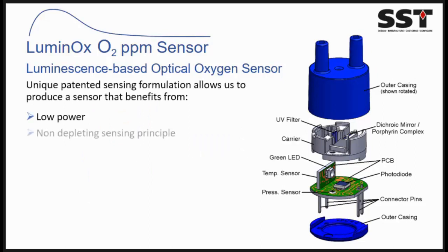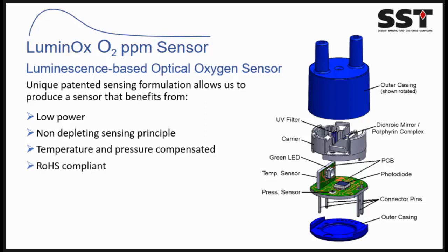This sensor, the most widely used ppm sensor on the market is by far electrochemical. There is electrochemical or zirconia and paramagnetic sensors. Here, just like electrochemical, this sensor operates at a very low power. So at 5 volts, this gives out less than 7 milliamps. It also has a non-depleting principle, and I'll explain what that means. For example, if ppm sensors based on electrochemical sensors are exposed to ambient conditions, like what we're in now, they start to deplete. The oxygen uses up the electrolytes. So you either have to basically change out the sensor itself or have frequent recalibration. This is something that we are trying to get round.